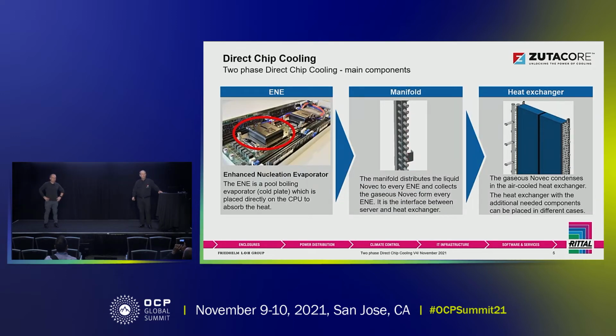What a system like this would consist of is three main components. There's the direct-on-chip evaporators, which we call ENEs, enhanced nucleation evaporators. There's also a manifold in the back of the rack, that all servers are connected to, and the manifold is connected to a heat rejection unit. What we have here is a heat exchanger, or the HRU or CDU as they're called. We have them on air, meaning they take cold air, condense it, and take hot air out, or based on facility water, to condense the NOVEC.